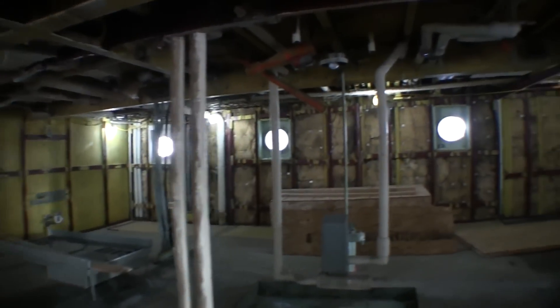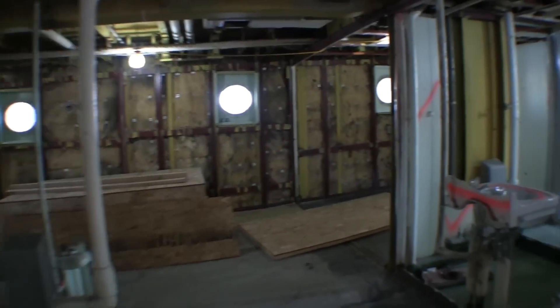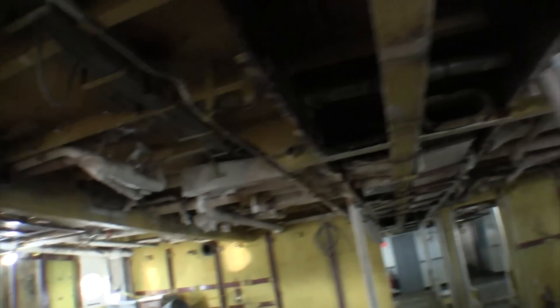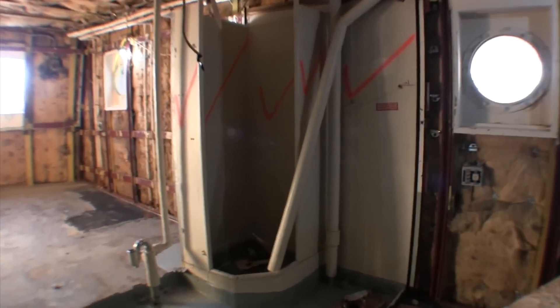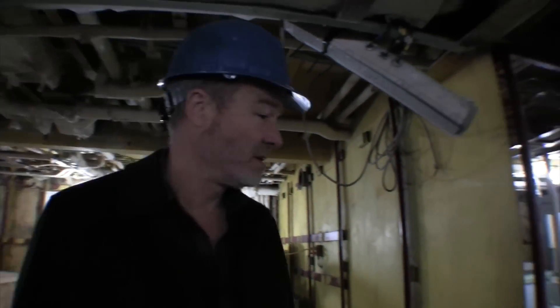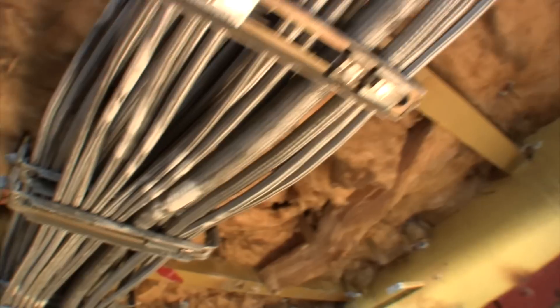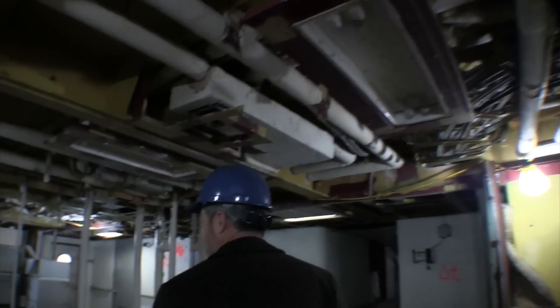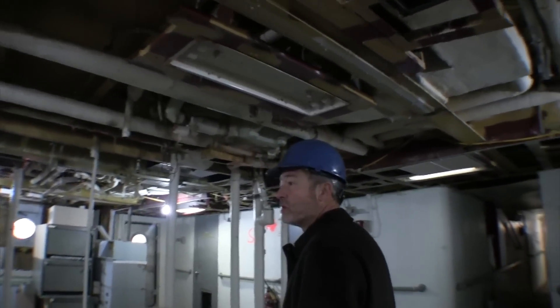You'll see that these walls have been taken back to the insulation. Overhead I'll show you some details of the wiring — they actually stripped out the plumbing in here but left the base of the showers and the sink piping. Why re-plumb when you've got the sewage lines and all of that here? All these cables have markings and tags on them — numbers that equate to circuits — so it's relatively easy to reuse a circuit.